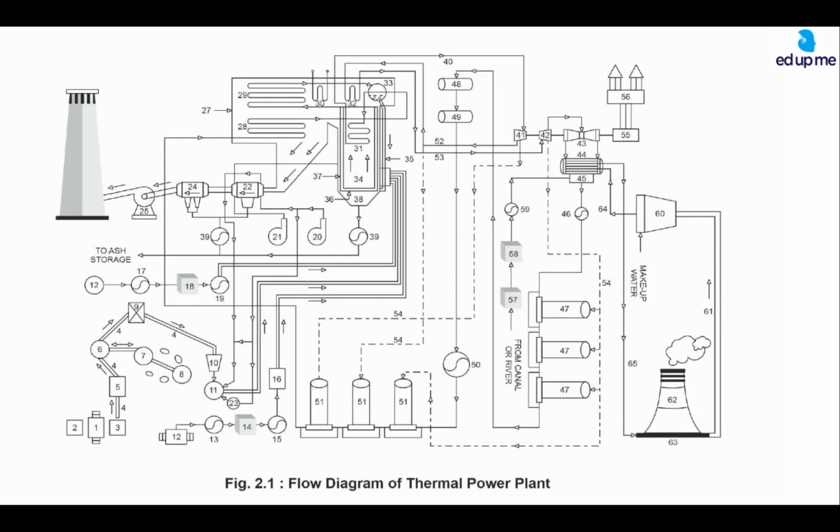You do not have to give more temperature in the boiler, right? Because the air preheater heats the air by the temperature of the flue gases themselves, because flue gases are coming out and they are passing through the air preheater. So that air is given to the boiler, and now the two airs, FD air and primary air, are mixed. Now the air is sufficient for combustion. So C plus O2 is equal to CO2 plus heat. So enough amount of heat is produced.